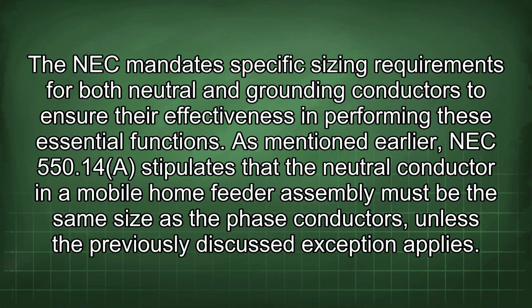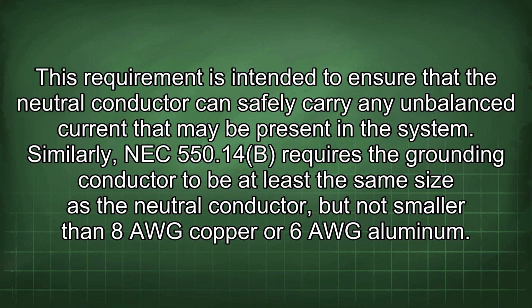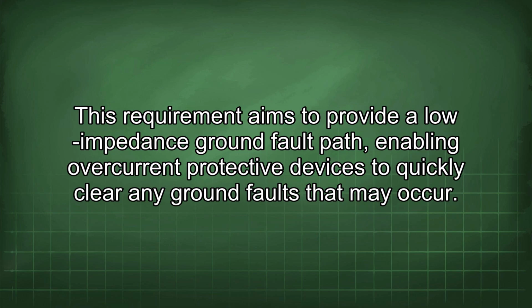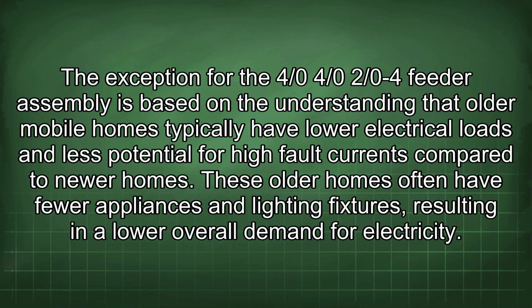functions. As mentioned earlier, NEC 550.14 stipulates that the neutral conductor in a mobile home feeder assembly must be the same size as the phase conductors, unless the previously discussed exception applies. This requirement is intended to ensure that the neutral conductor can safely carry any unbalanced current that may be present in the system. Similarly, NEC 550.14b requires the grounding conductor to be at least the same size as the neutral conductor, but not smaller than 8 AWG copper or 6 AWG aluminum. This requirement aims to provide a low impedance ground fault path, enabling overcurrent protective devices to quickly clear any ground faults that may occur.